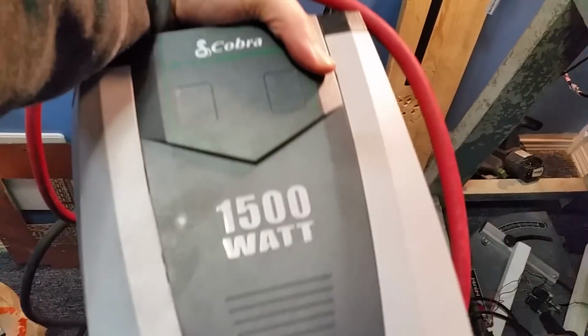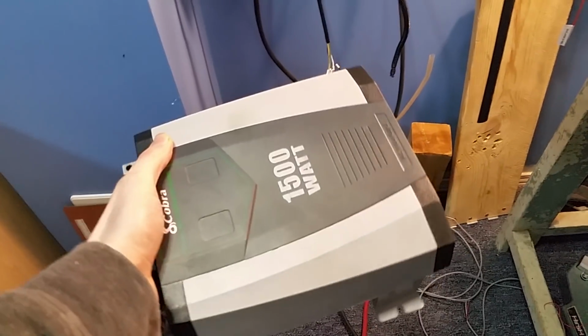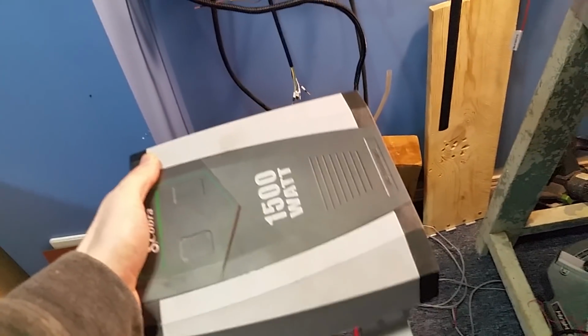Those cheap inverters don't have surge capability. I have one laying around here somewhere... ah yes, here it is. This lightweight 1500 watt unit is a high frequency inverter, there's no transformer inside it. It's cheap, but if you're not pulling a surge current, like running a vacuum cleaner or something like that, this will work just fine. If it's just for computers, laptops, lamps, LED lighting, this is totally fine, it'll do the job.